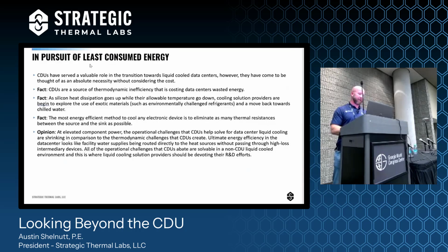Okay, call to action. So just a few fun facts here. CDUs have served a valuable role in the transition towards liquid-cooled data centers. However, they have come to be thought of as an absolute necessity without necessarily considering the cost, and I'm not talking about the dollar cost. Fact, CDUs are a source of thermodynamic inefficiency that is costing data centers to waste energy. That's true. We just talked about it.